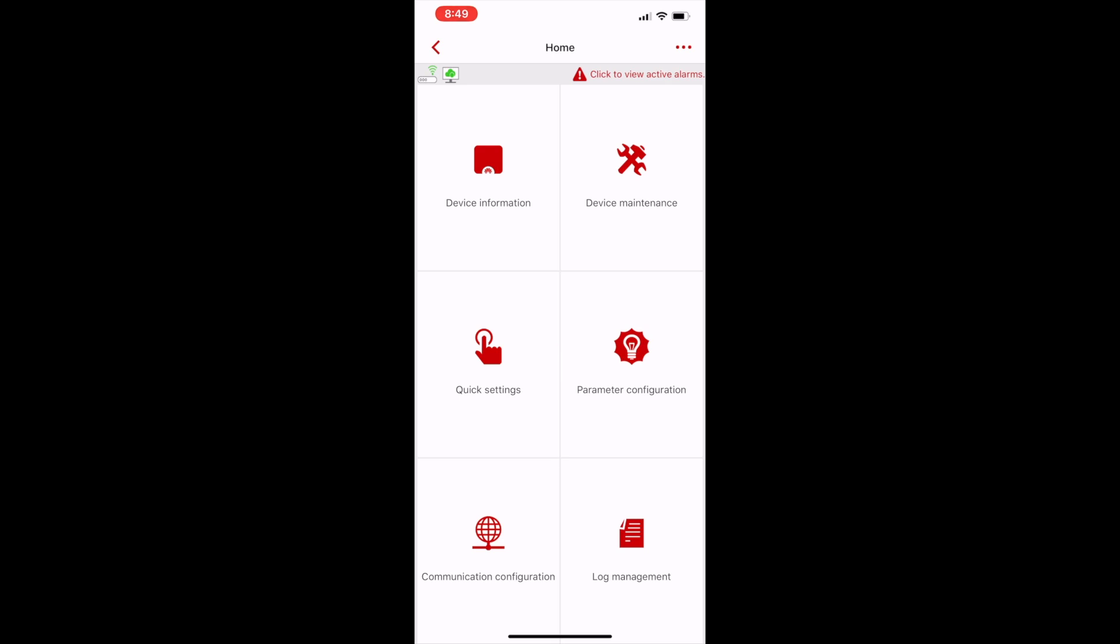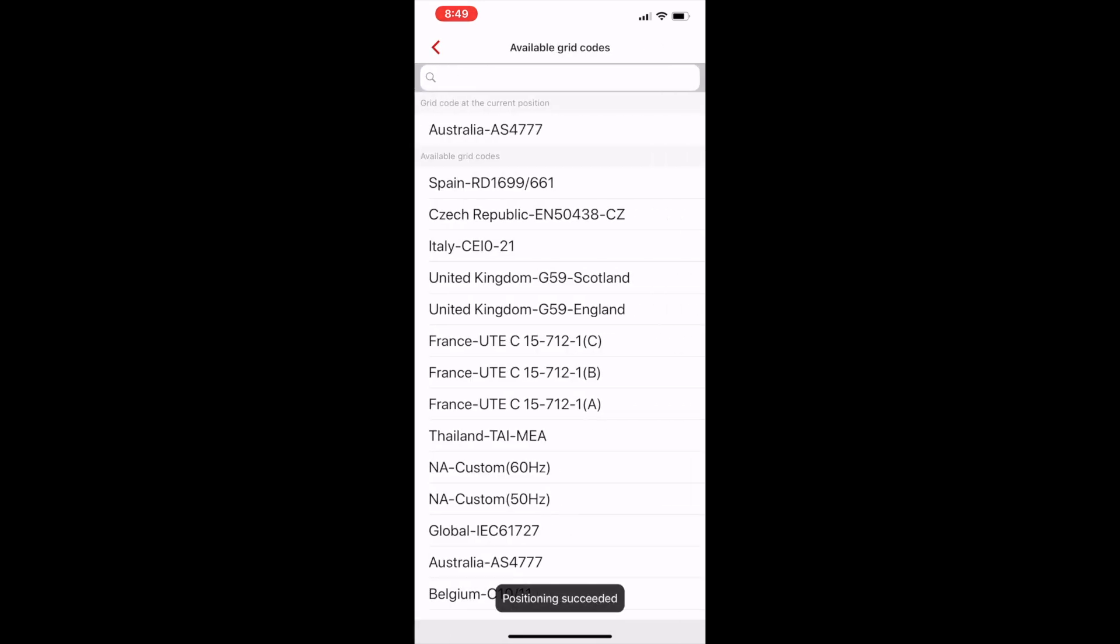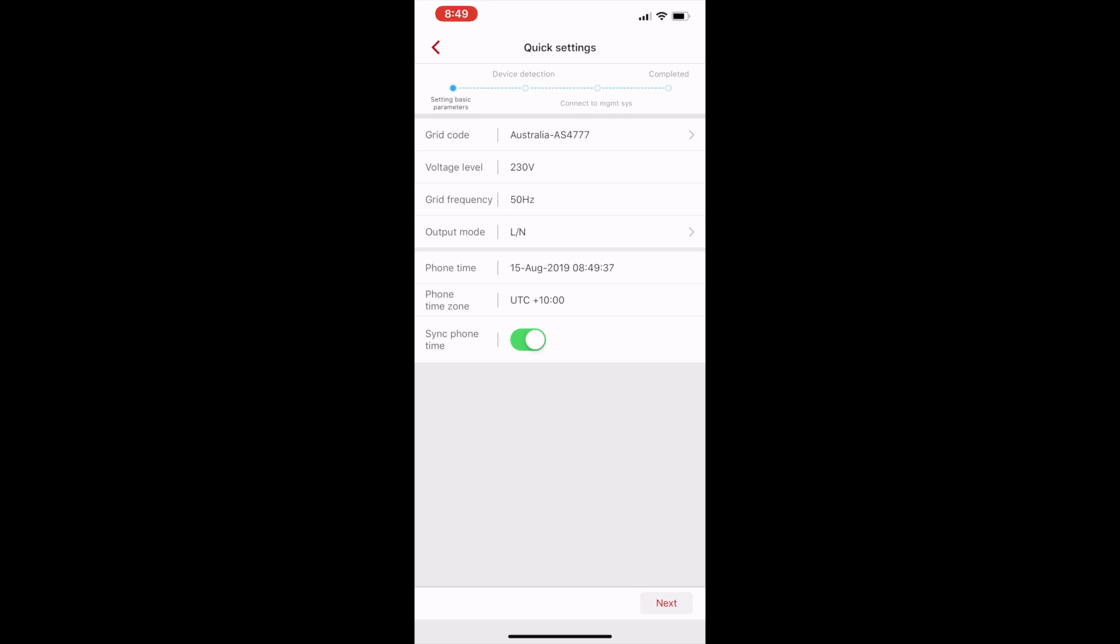There's a range of tabs you can select. The quick settings gets you started. You can select your grid code. In this case, Australia 4777, sync the time with the phone, and confirm your settings.